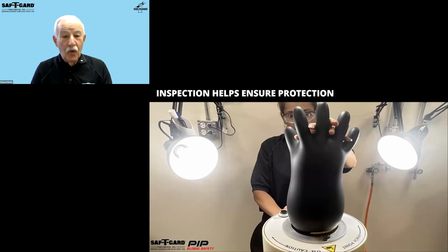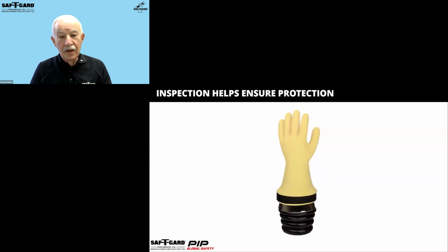Take care of it. In the qualified inspection facility, inspecting these gloves identifies physical, chemical, or ozone damage. When trained inspectors do this in an inspection facility, direct light is recommended because it enhances the ability to see any surface imperfections in the rubber. Inflating the gloves with air or otherwise stretching the surface helps identify age and ozone damage, as well as any other physical damage, such as snags, rope burns, deep cuts, and punctures. A portable mechanical inflator may be used in the field to enhance the inspection of the glove by simply affixing the glove to the inflator and pumping it up.